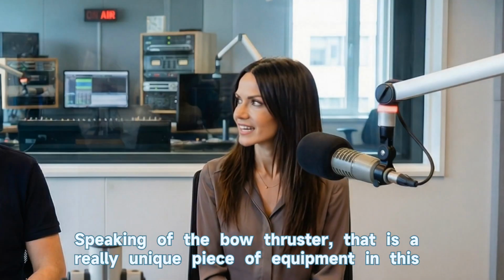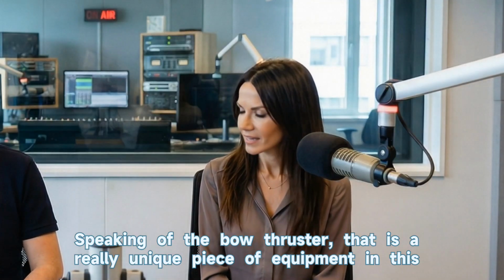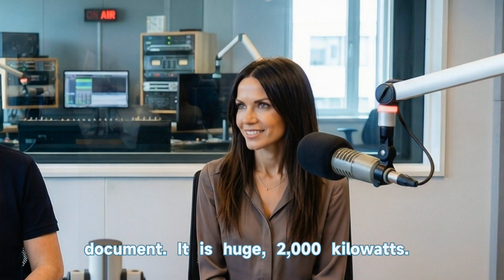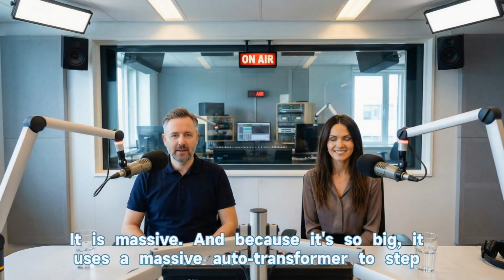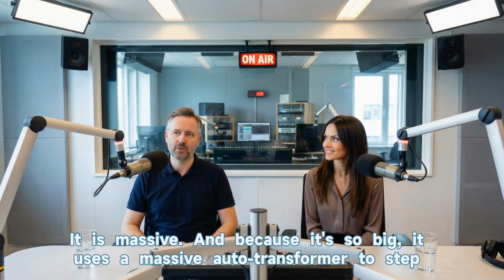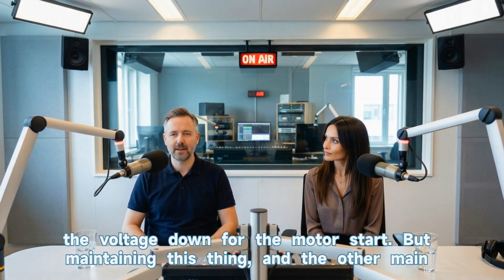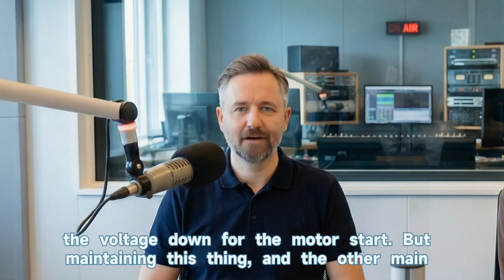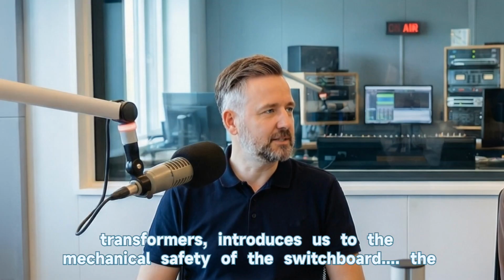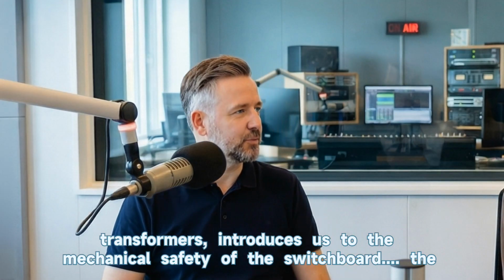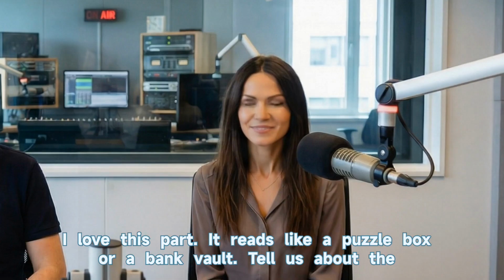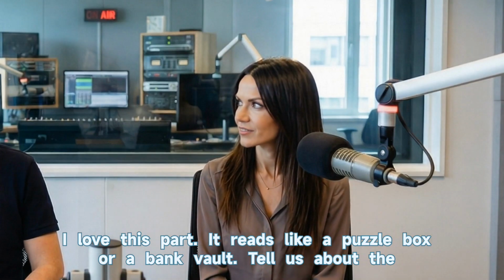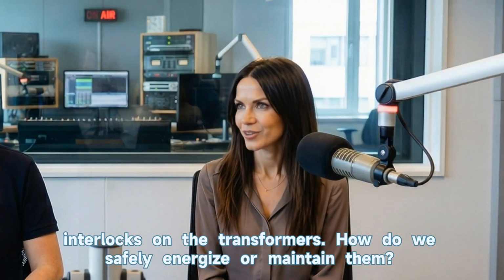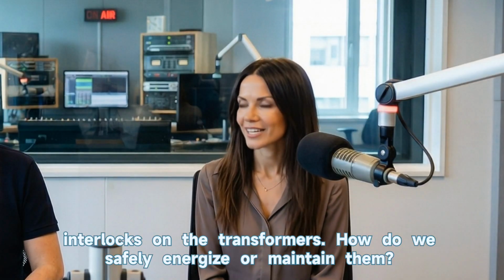Speaking of the bow thruster, that is a really unique piece of equipment in this document. It is huge, 2,000 kilowatts. It is massive. And because it's so big, it uses a massive auto transformer to step the voltage down for the motor start. But maintaining this thing and the other main transformers introduces us to the mechanical safety of the switchboard. The keys. I love this part. It reads like a puzzle box or a bank vault. Tell us about the interlocks on the transformers. How do we safely energize or maintain them?